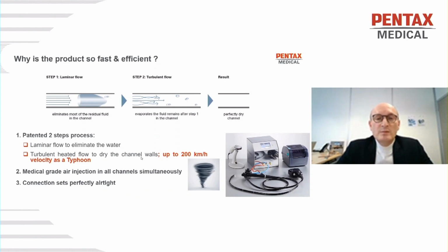The second important thing is the medical grade air injection, which is done simultaneously in all channels. And finally, we have a connection set which is perfectly airtight. So the flow coming from the Plasma Typhoon system goes inside the channels without leakage outside, in order to have the right velocity, the right temperature, and the right flow rate for an efficient drying.